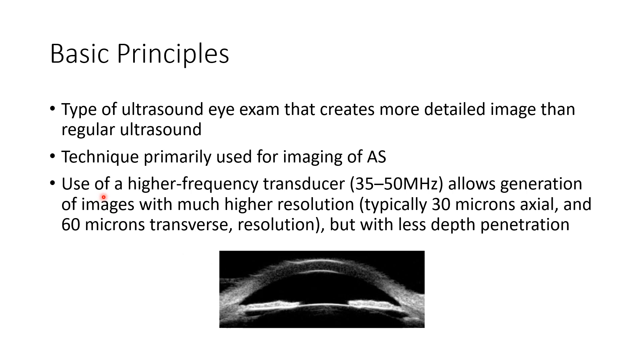In ultrasound biomicroscopy, we use a higher frequency transducer with a frequency of 35 to 50 megahertz, which allows generation of images with much higher resolution. The resolution is typically 30 microns axial and 60 microns transverse. It has less depth penetration because of the higher resolution.